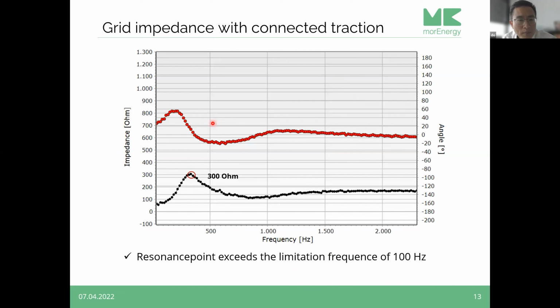Now we have a grid impedance measurement when the traction is connected into the grid. You can see a damping effect when the traction is connected into the grid, so we have a much lower level of the absolute value of the impedance. Also the resonance frequency shifted to some higher frequency.